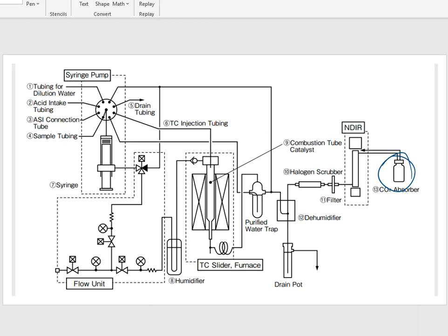Well, the issue is that this machine generates CO2, and this CO2 was a concern for some people. And there was a regulation that was put in place, and because this machine is generating carbon dioxide, again, you're breathing it out, this machine's breathing it out, they believed that they should have a CO2 absorber on that machine just to absorb all of the extra CO2 that this machine might be producing.